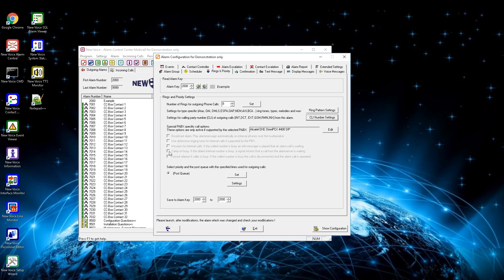Fourth option is camp on busy: if the dialed phone is in a call, MobiCall tries to reach the device when it becomes available again. Fifth option is force release, which disconnects an existing call and repeats the alarm call to the receiver. The last option on this page is for priorities — here you can set which queue the calls shall be made on, and within the queue the available lines can be defined for every queue.